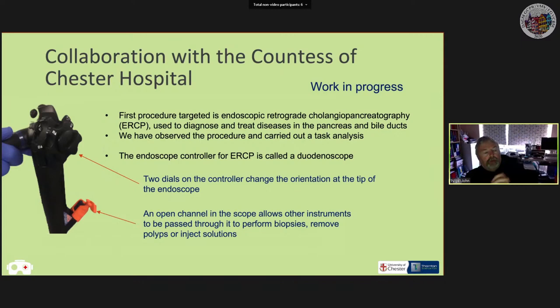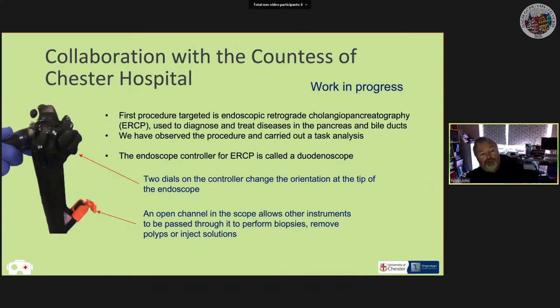The picture on the left shows the endoscope controller — for ERCP it's called a duodenoscope. It has a couple of dials used to control the orientation of the tip of the endoscope. The fibre optic wire goes through that controller and into the patient. There's also an open channel allowing other instruments to pass through for biopsies or injecting contrast agent.